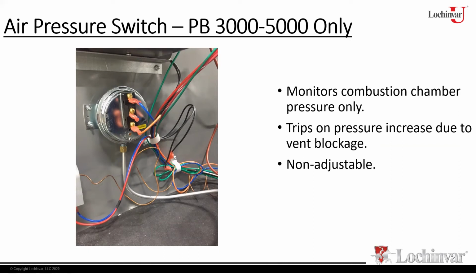The reason the 2.5 doesn't get one is that when we go through our certification, there is a test, and basically it's a block vent test. They take the unit and fire the heater up at 100% at its maximum capacity, and then they start blocking the vent off. As they're blocking the vent, they're looking at the combustion. If the heater will shut off on flame signal or just shut off on its own before the combustion goes bad, then at that point I don't need a pressure switch, because the heater is going to shut off on its own before the combustion is really out of whack, and I don't have to worry about it. My 2.5 million will do that. It will shut off before we get to that point.